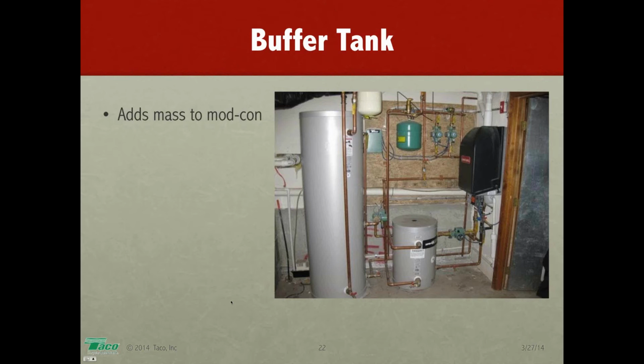Buffer tanks are just big hydraulic separators. There's nothing remarkable or unusual or fancy about them. It's just a big old honking hydraulic separator. The one you're looking at here, that little itty bitty tank, also happens to be insulated. Okay, it's an insulated tank. It's just a big empty tank where we store water. We're adding water volume to the boiler to essentially help keep it from short cycling under milder conditions, and also help keep it from short cycling when it's really hot out or really cold out too.